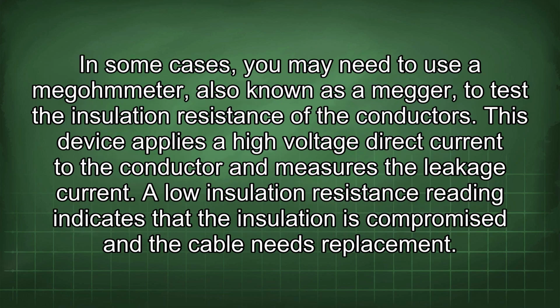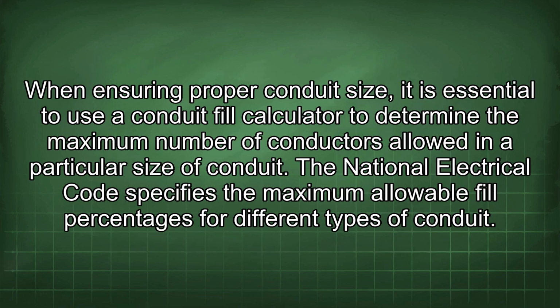In some cases, you may need to use a megohmmeter, also known as a megger, to test the insulation resistance of the conductors. This device applies a high voltage direct current to the conductor and measures the leakage current. A low insulation resistance reading indicates that the insulation is compromised and the cable needs replacement. When ensuring proper conduit size, it is essential to use a conduit fill calculator to determine the maximum number of conductors allowed in a particular size of conduit.